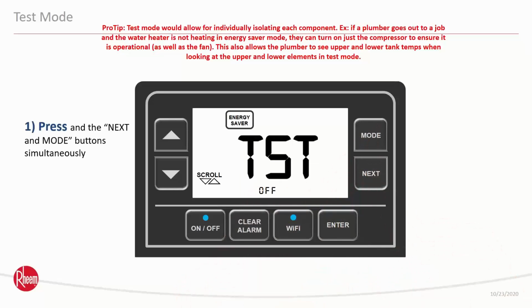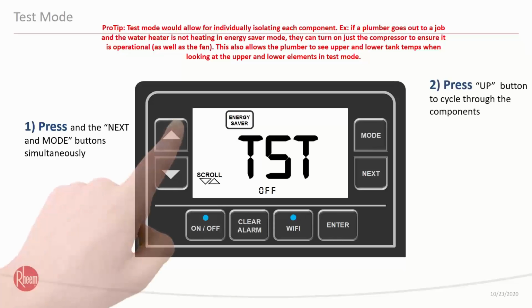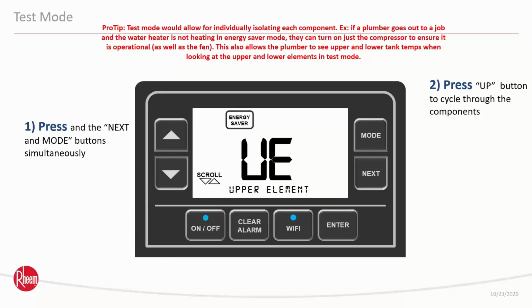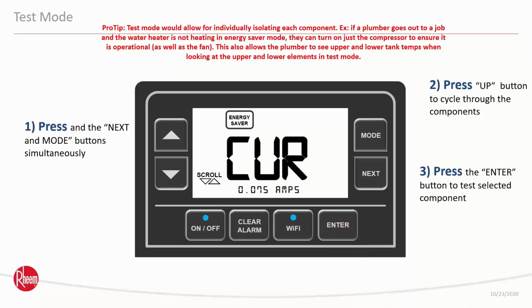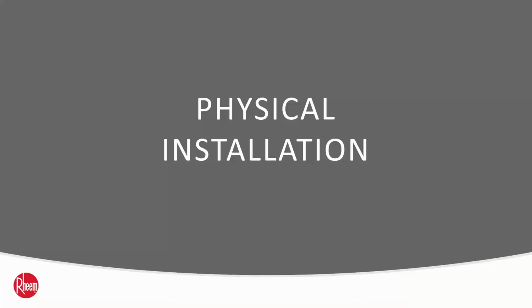it. Press both simultaneously. You're going to go into test mode, press the up, go to the upper element, enter, and it's going to show you how many amps that element's pulling. Physical installation.